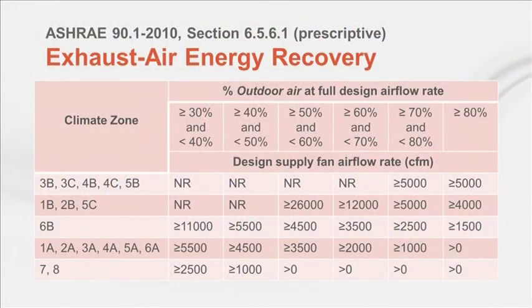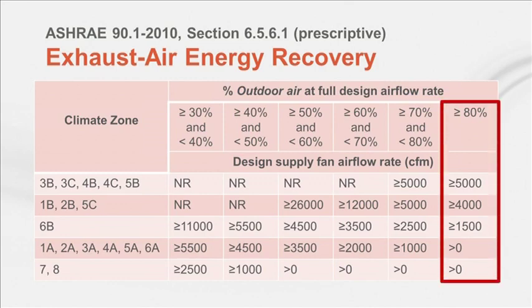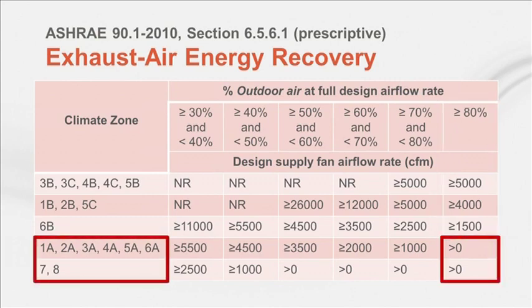The last 90.1 topic is exhaust air energy recovery. Similar to economizing, the standard 90.1 requirement for energy recovery depends on the system size and climate zone, but also on the percentage of outdoor air. The most common interpretation of this table is that if a 100% outdoor air system is installed, the furthest right column applies. In this case, if the project is in a humid climate, designated as A, or one of the coldest climates, 7 or 8, then the dedicated outdoor air system must have exhaust air energy recovery.